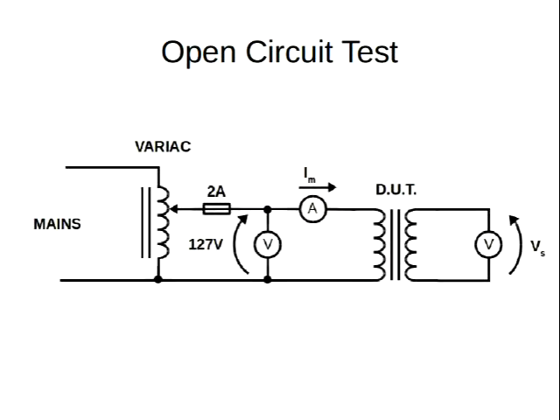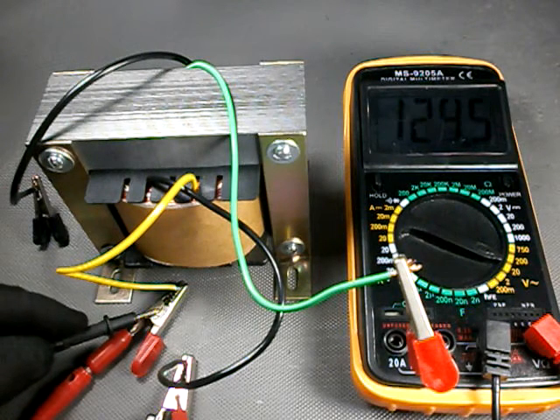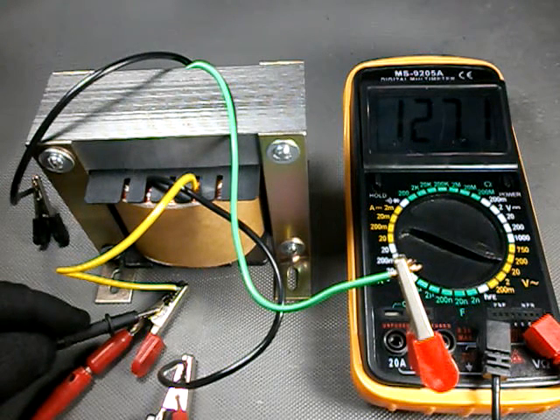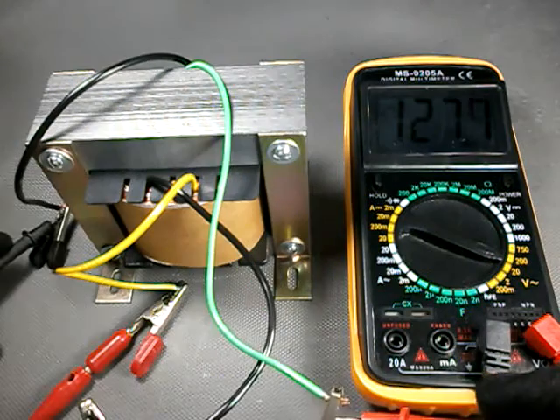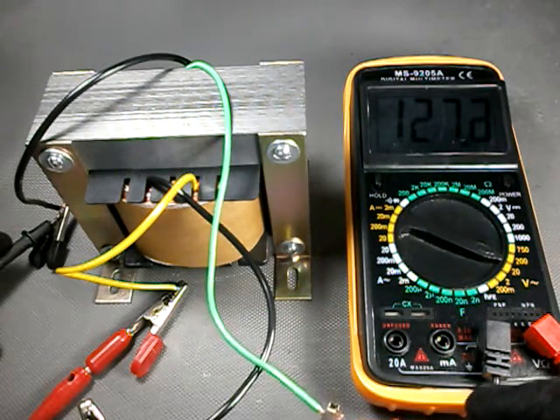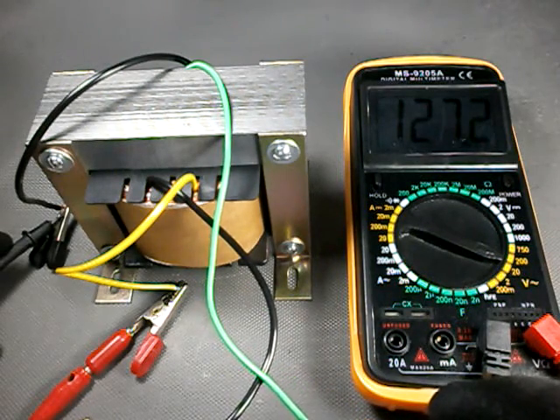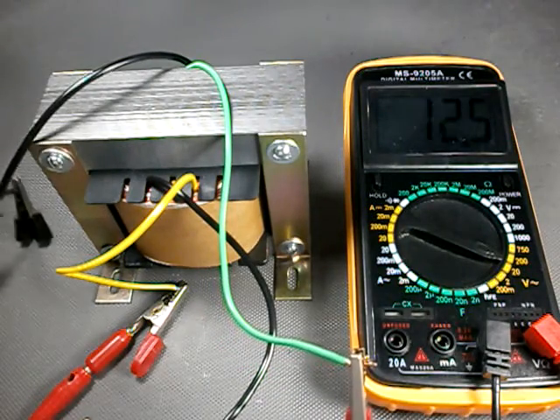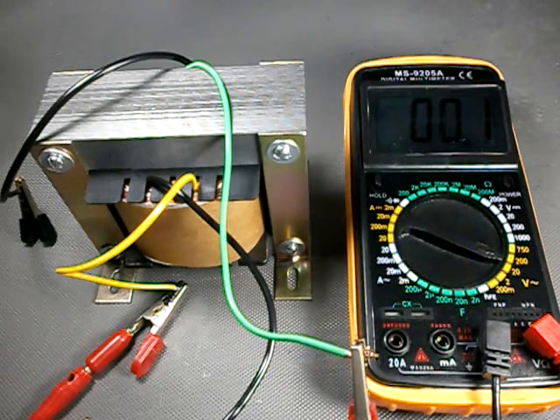Next we go to the open secondary test, in which we measure the secondary voltage and the primary idle current, which in this case will be equal to magnetizing current plus the core loss current. And there we have it. The voltage on the primary is 127 volts, and on the secondary is 127 volts also. Very nice. That indicates that the turn ratio is exactly 1:1.